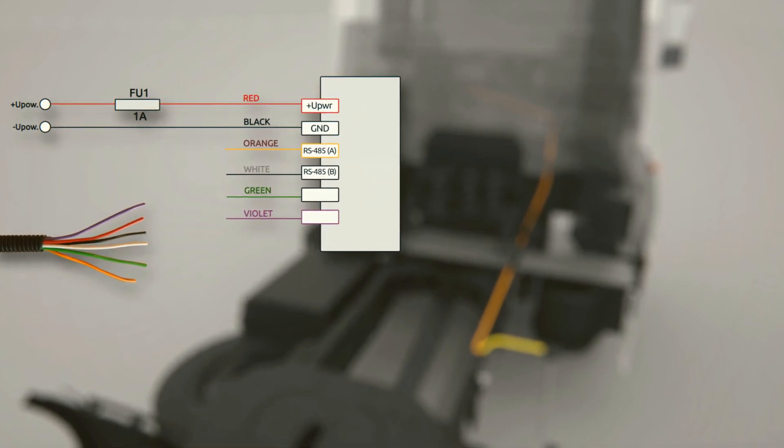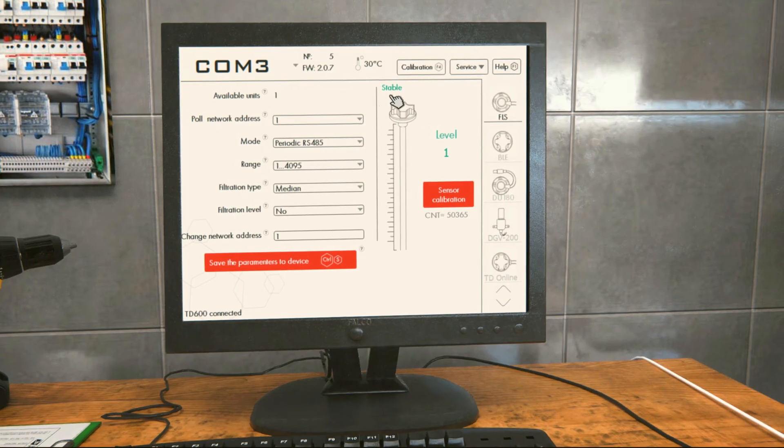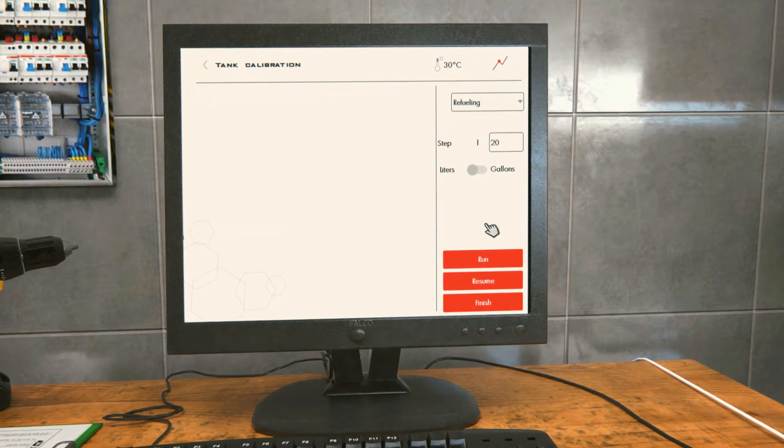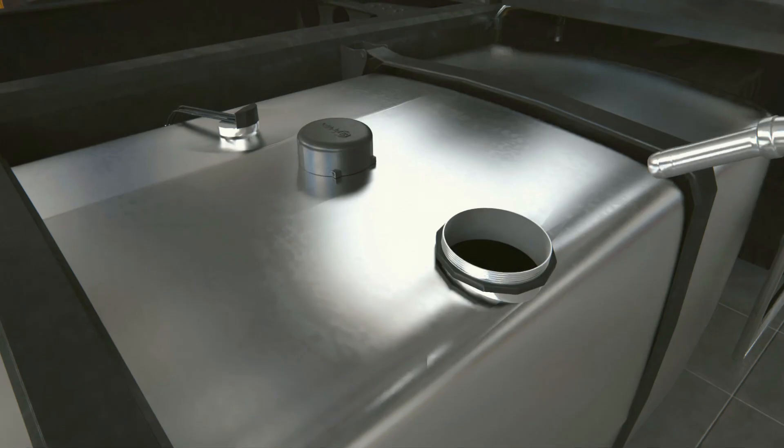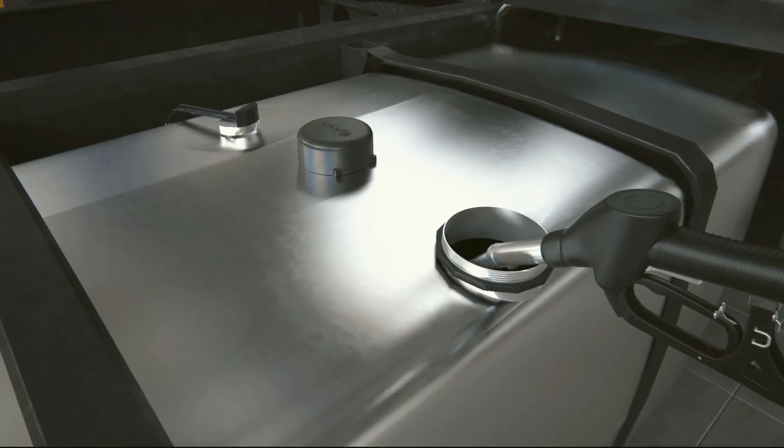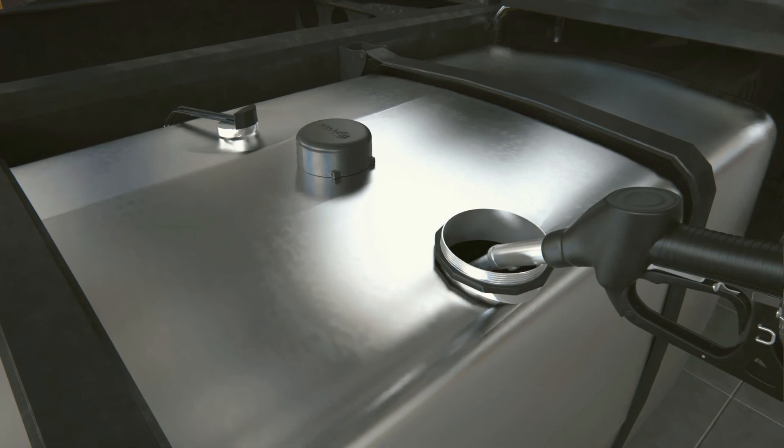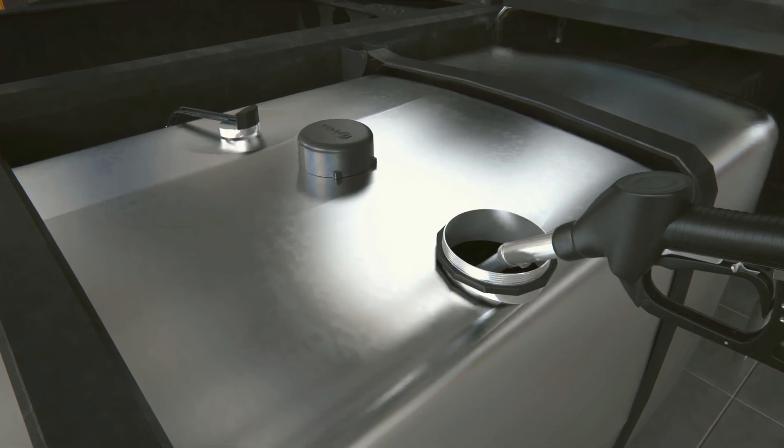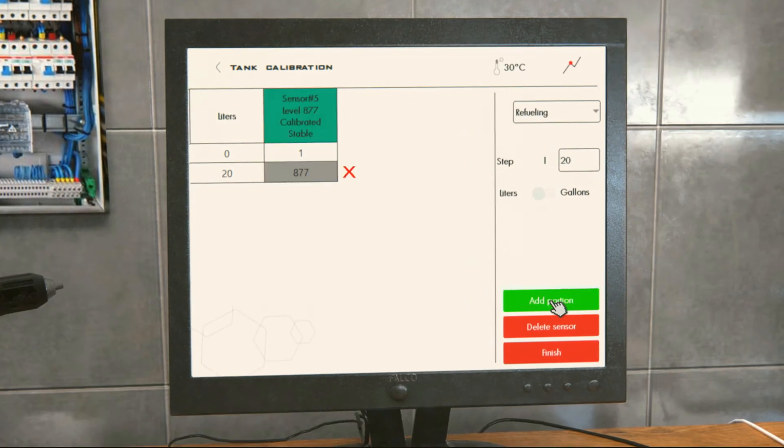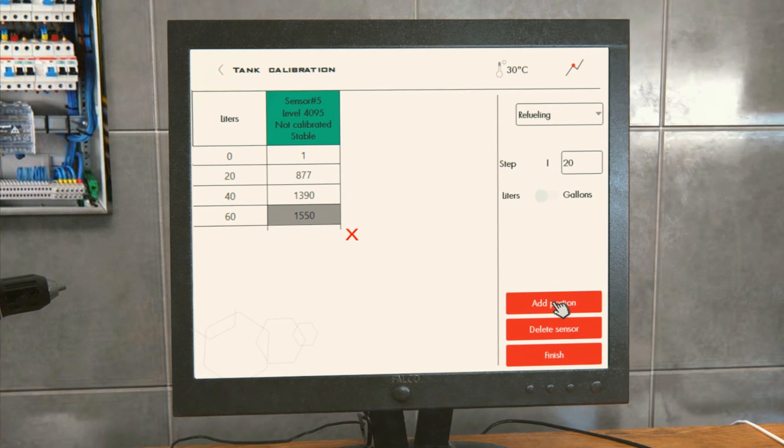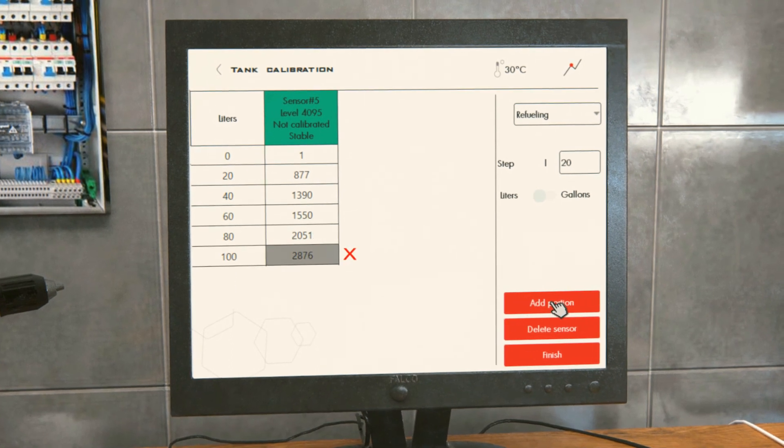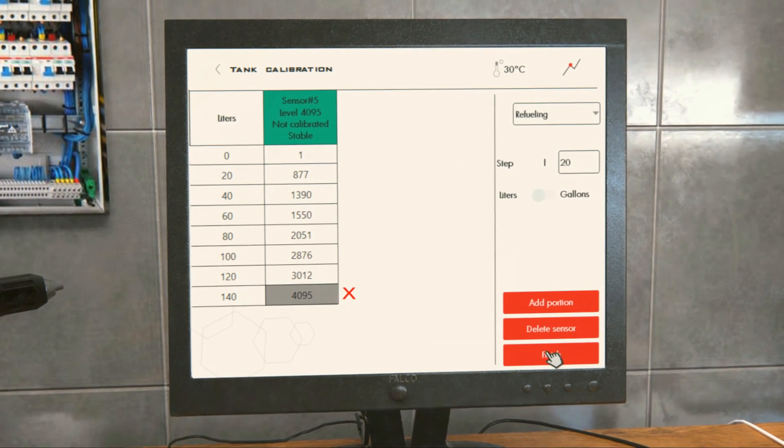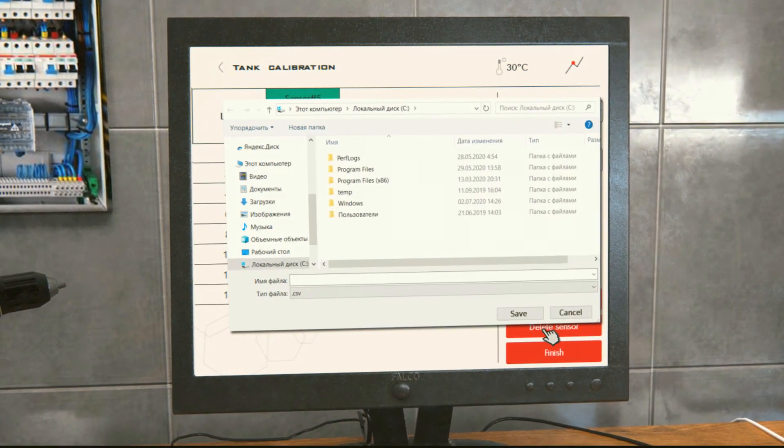Tank calibration on PC. Click the calibration and then run buttons. Similar to the wireless sensor, pour several portions of fuel, for example 20 liters, into the tank. During the procedure, click the add portion button after each portion is added and the level is stable. After that, hit the finish button and save the table.